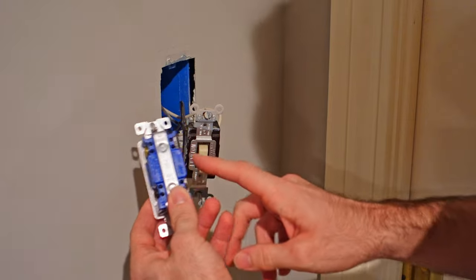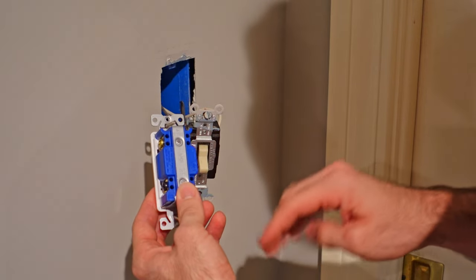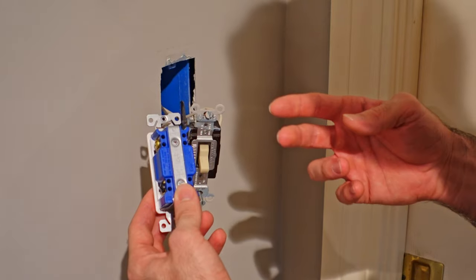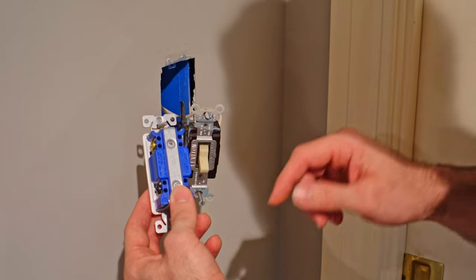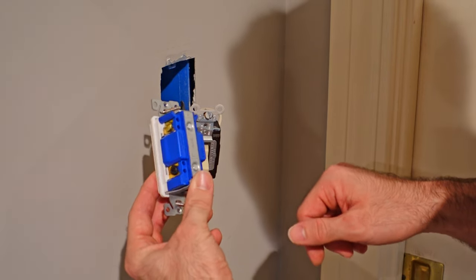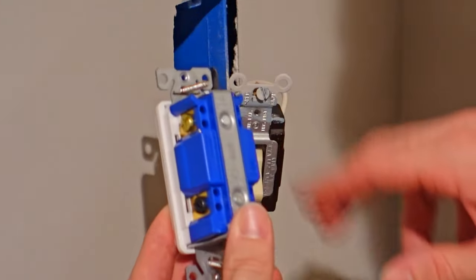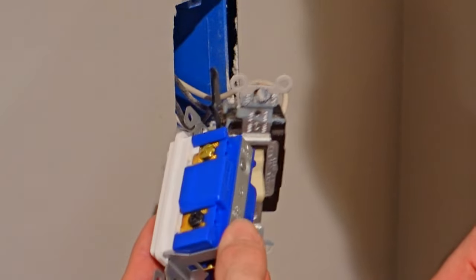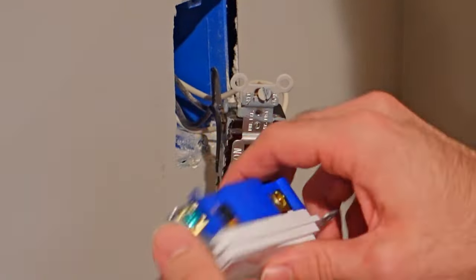What makes a four-way different from a three-way is that your three-way has three terminals on the back plus the ground — two gold, which are your travelers, and then one black terminal, which is your common. For a four-way, essentially what you do is add a second common. So you have two golds and two blacks, and then you still have your green ground terminal down at the bottom.